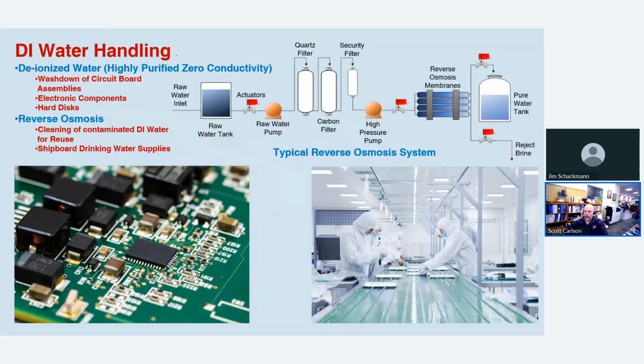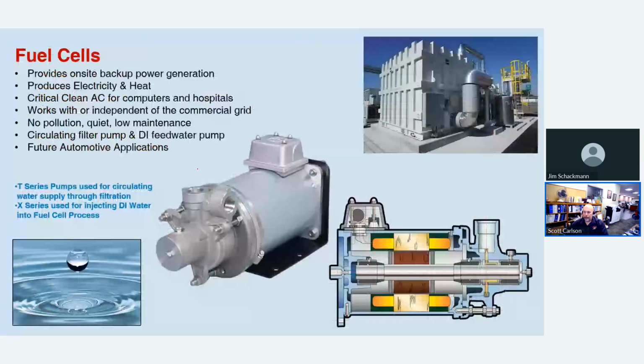Deionized water handling with our regenerative turbine pumps. We have a sealless can version of it that gets used quite a bit for anything that has deionized water that needs to be extremely clean. So washdown of circuit boards, other electrical components, any kind of reverse osmosis system can use our pumps. Here's our sealless can motor pump.